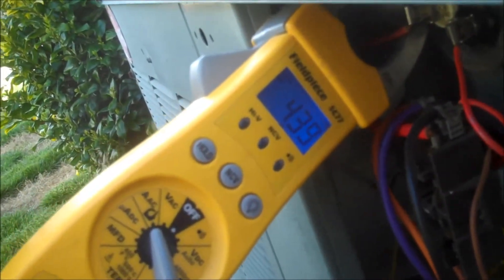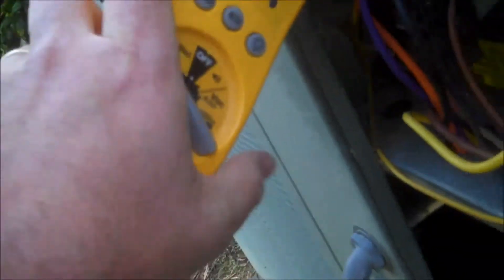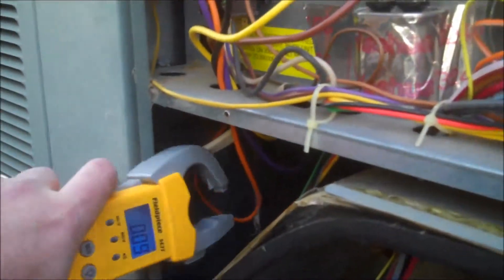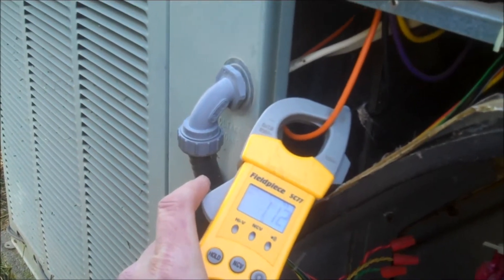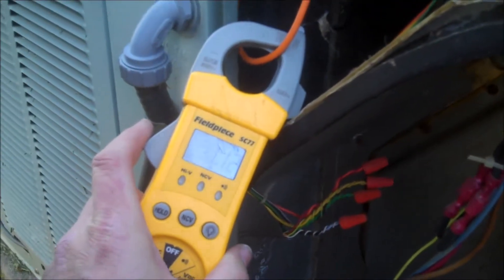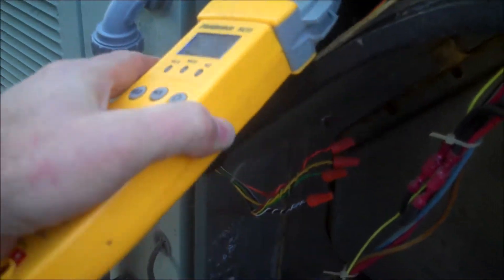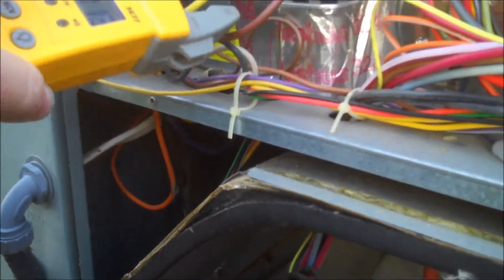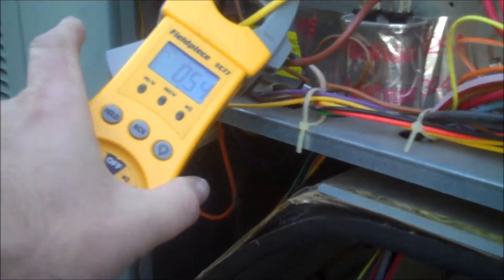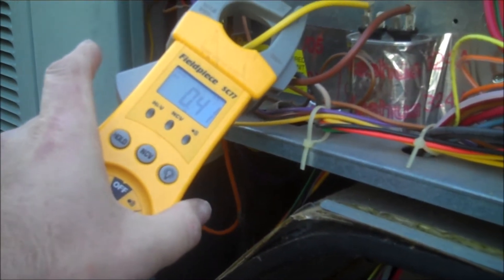You can see that we're at 4.4 on there. And then we'll look at the fan run amps, there at 1.1. The fan start amps at 0.4.